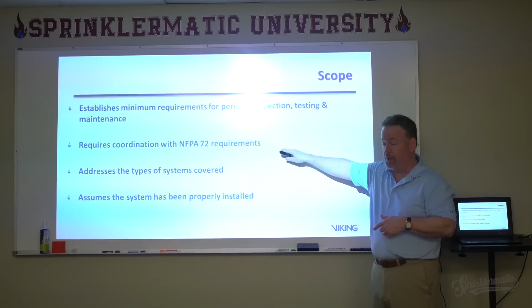It assumes that the system has been installed properly, and this is really, really important. This is really critical for the inspection technician to understand going into this: it assumes that the system has been installed properly. It's necessary to assume that, but it's also proper to assume that, because a system that's been installed in accordance with NFPA 13 has been approved by the authority having jurisdiction, and the building has a certificate of occupancy. All that documentation put together would lead us to believe that the system's been installed properly.